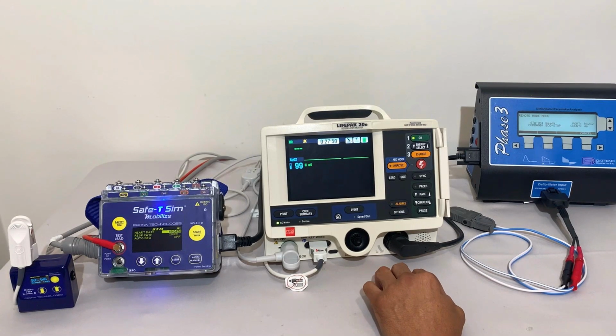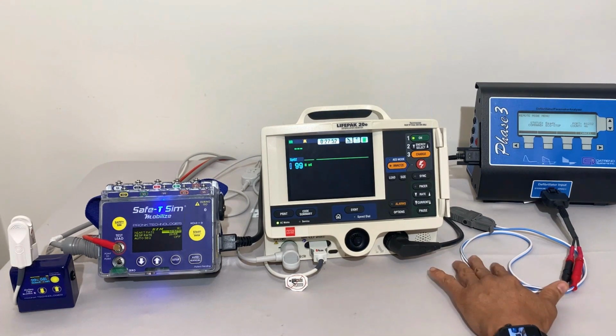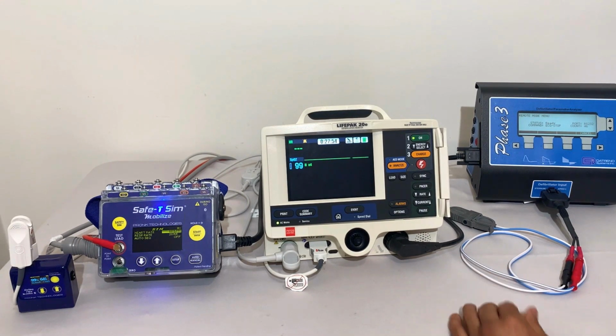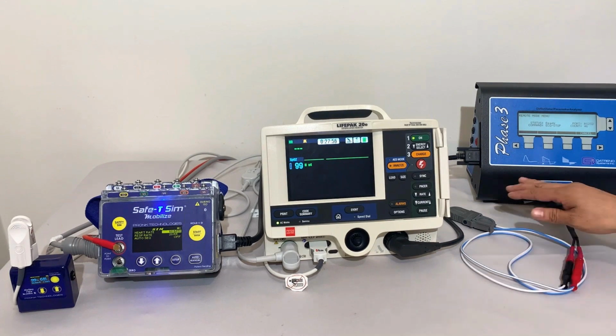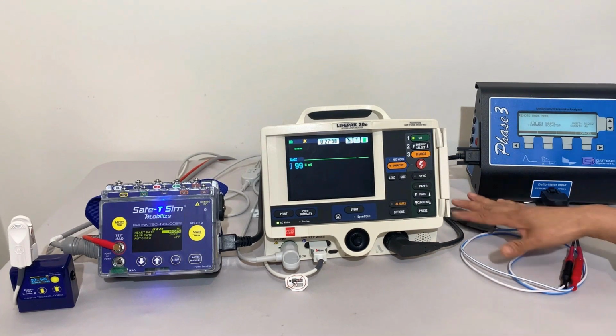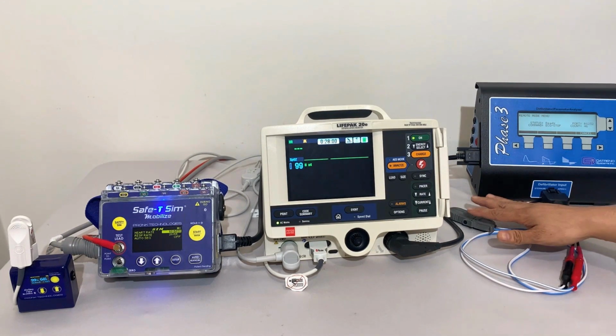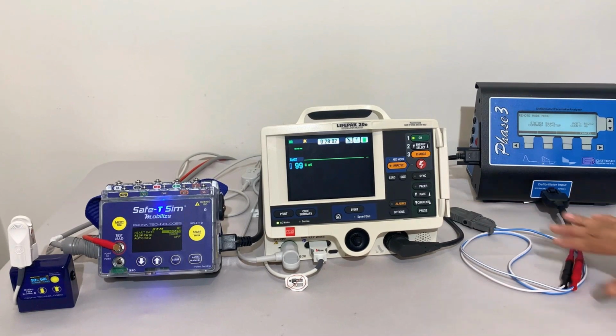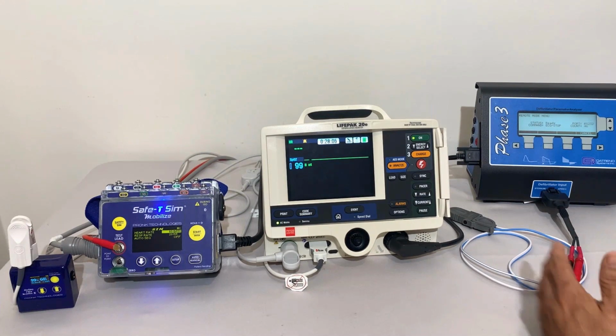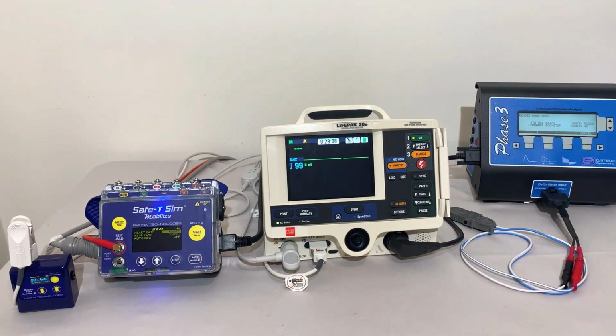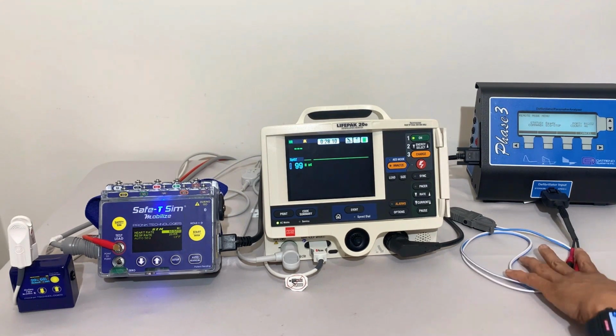Proceed to do the shock test. We want to, again, just verify that we've connected our defibrillator with the quick combo cable to the defib analyzer. In our case, we're going to do the quick combo cable test for the shock test to demonstrate that for you. Of course, we could do this by connecting the paddles up to the defib analyzer as well. We're going to start with quick combo cables.